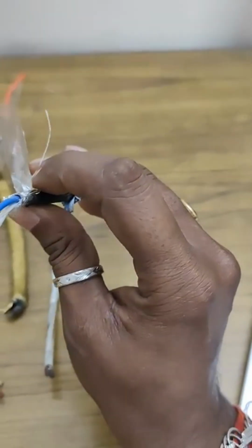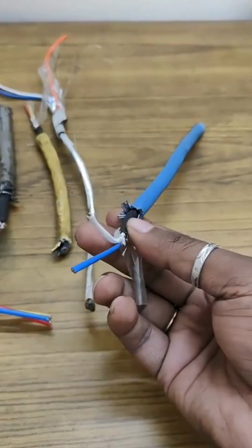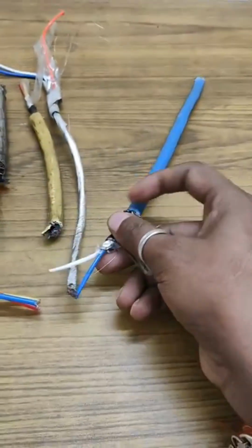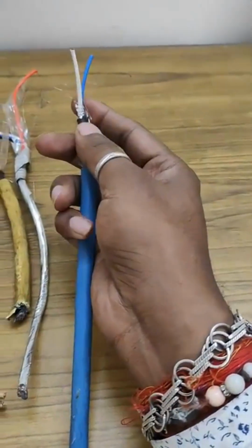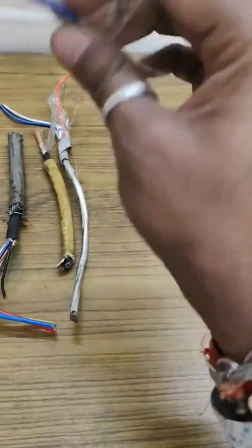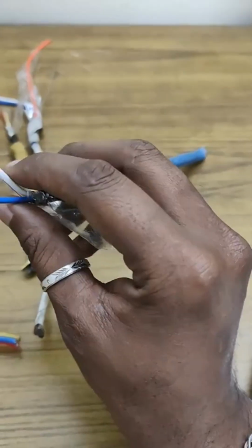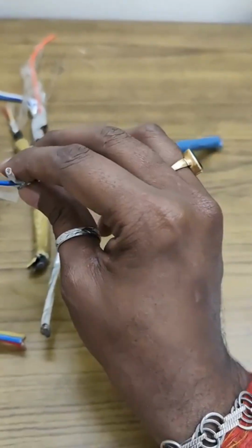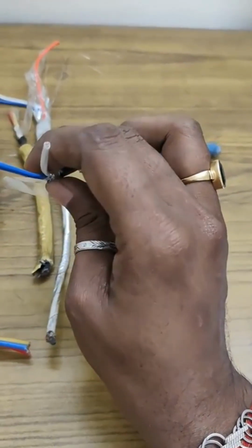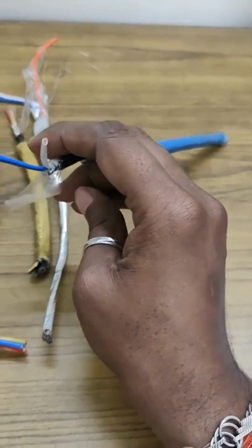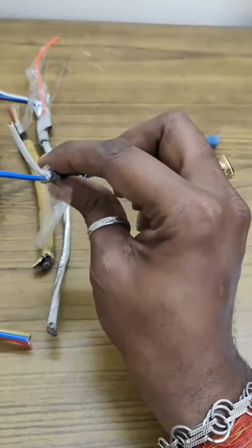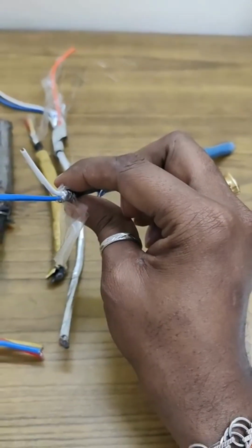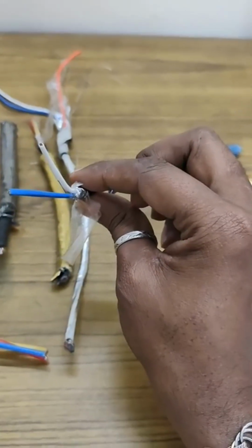First, this is a one-pair instrumentation cable. This is also commonly called a signal cable. One of the most important specifications when ordering this cable is capacitance per meter. Capacitance is a very important factor in any signal cable, especially when the cable is used over long distances, because a 4 to 20 milliamp signal will respond slower if the cable capacitance is high. Higher capacitance can also increase noise pickup, and if this cable is used in a fast control loop, you may clearly notice that the data starts lagging slightly.